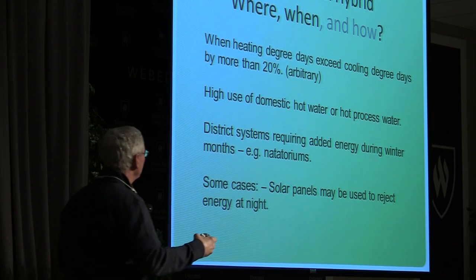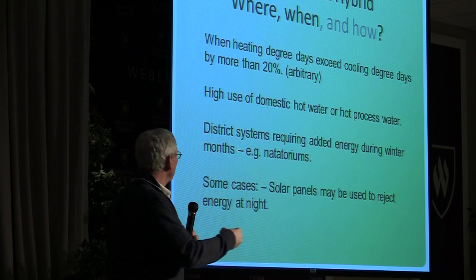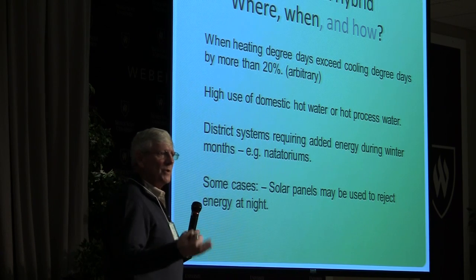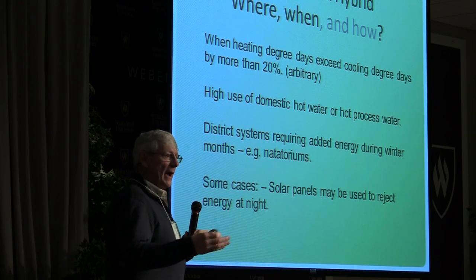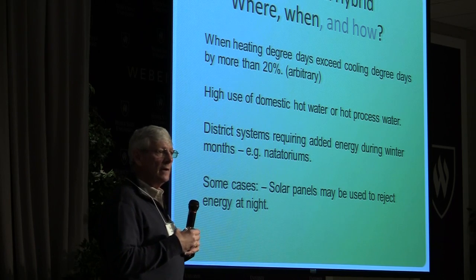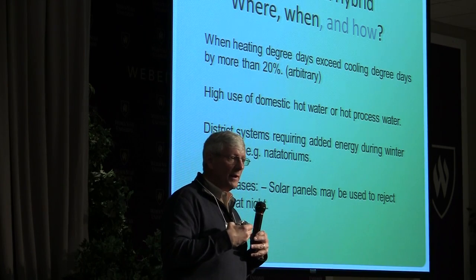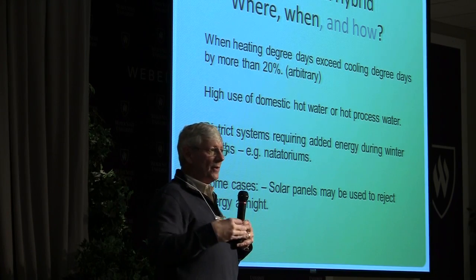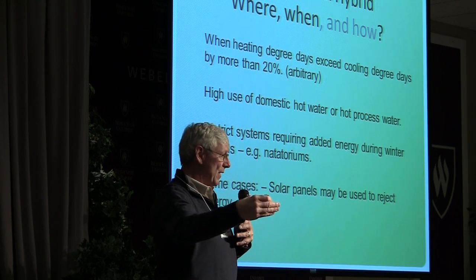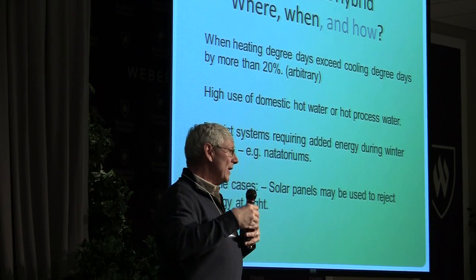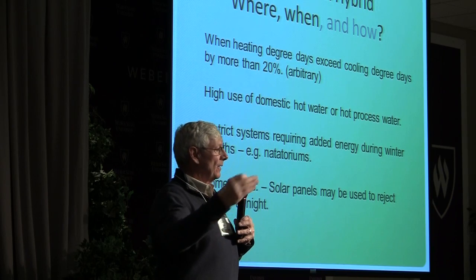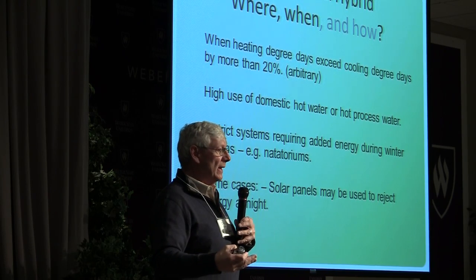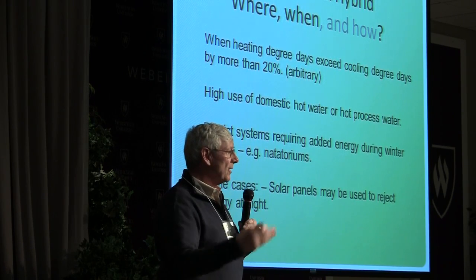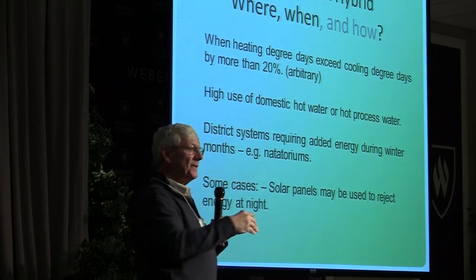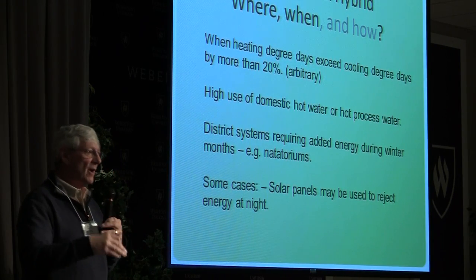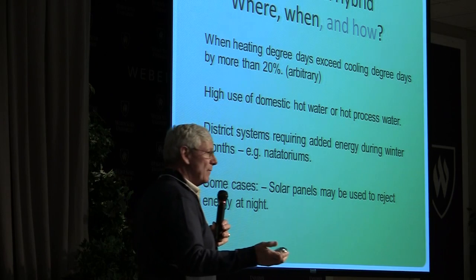When the heating degree days exceed the cooling degree days by more than about 20%, that's an arbitrary number, you get a net negative energy pull, taking extra energy out of the ground source. If I were to take a little bit of solar and trickle charge it, feed it back into the loop, I could restart almost every year. I could actually set the system back to normal or native ground temperature, the most optimum temperature for the heat pump.